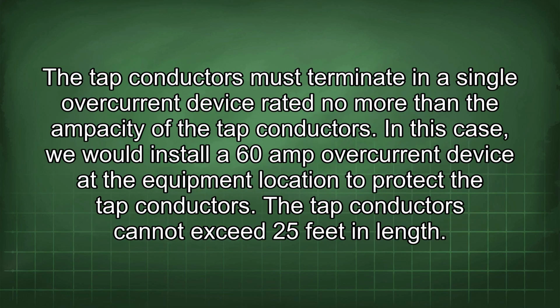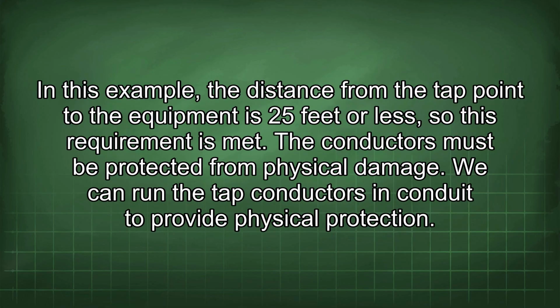The tap conductors must terminate in a single overcurrent device rated no more than the ampacity of the tap conductors. In this case, we would install a 60 amp overcurrent device at the equipment location to protect the tap conductors. The tap conductors cannot exceed 25 feet in length. In this example, the distance from the tap point to the equipment is 25 feet or less, so this requirement is met. The conductors must be protected from physical damage. We can run the tap conductors in conduit to provide physical protection.